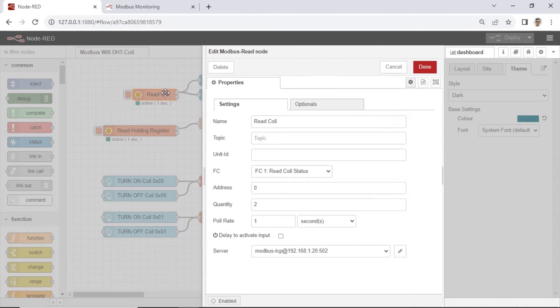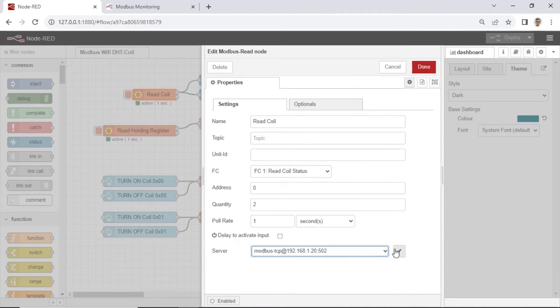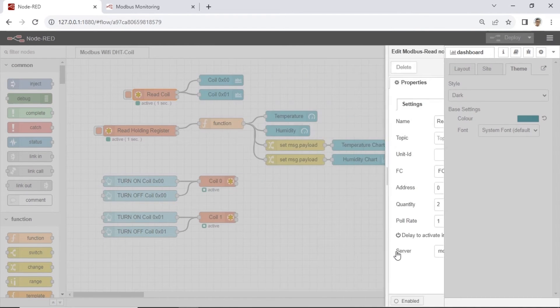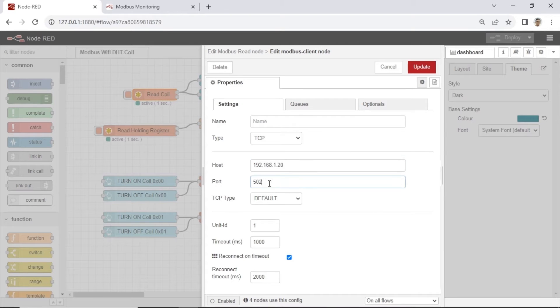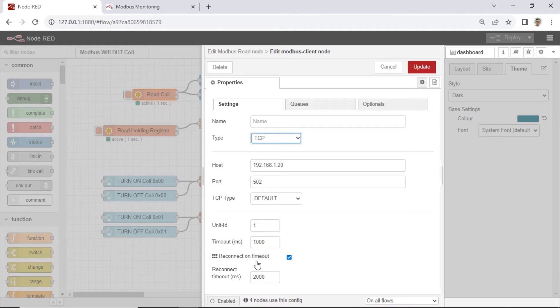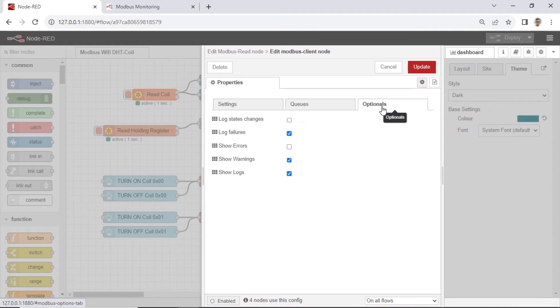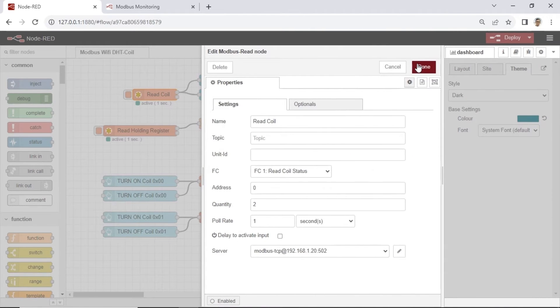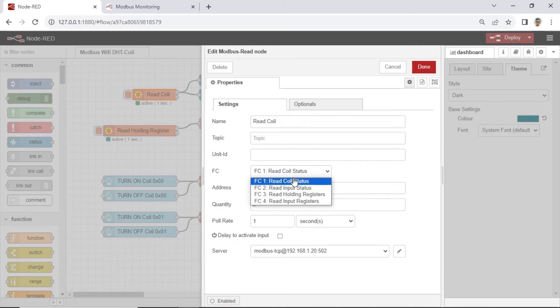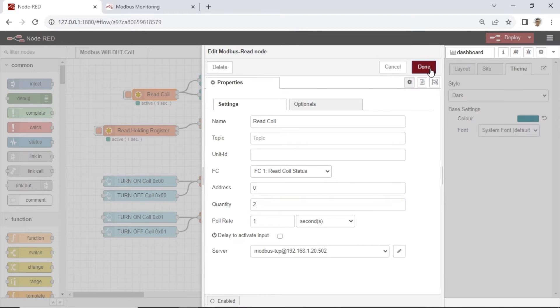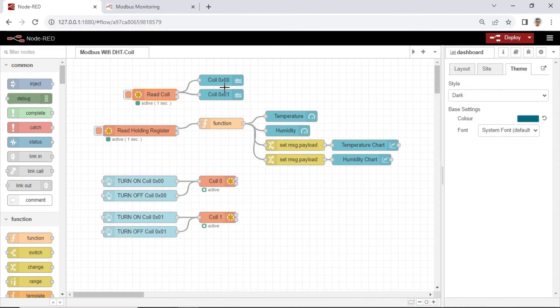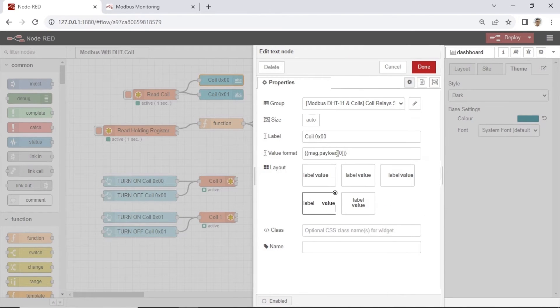This is the Node-RED flows. I use Modbus node to read and write the Modbus TCP server. Configure the server, set the IP address, port number and set the type to TCP. To read coil status select function code to read coil status. Then set the starting address to 0 and quantity is 2. It means it will read status address 0 and address 1.